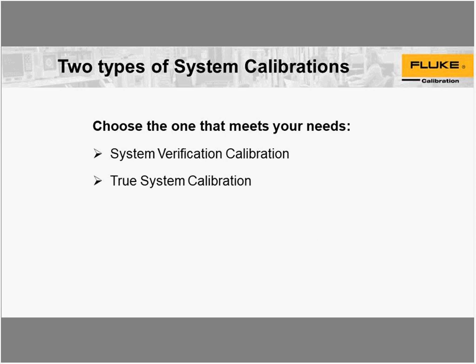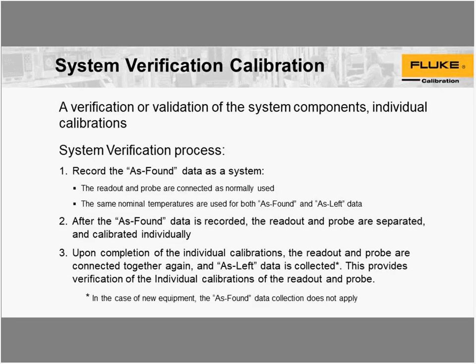Right. There are two types of system calibrations. One, system verification calibration, and there's a true system calibration, or loop calibration, as it's sometimes called. System verification calibration consists of verifying two individual units that have individual calibrations.